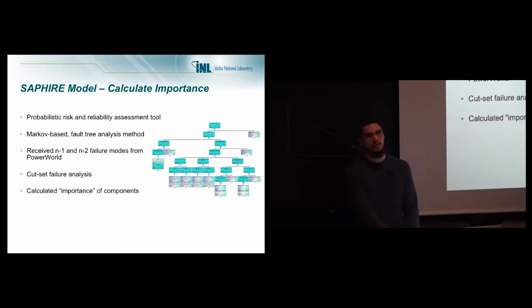We passed that cut set information into SAPHIRE, a probabilistic risk assessment tool based on fault trees. All we did was model those component combinations and the probabilities of failure for those components based on generic North American grid data. So how often do transformers fail in the United States? That's how often we chose to make them unavailable in our system, and calculated the probabilities of those failures occurring.